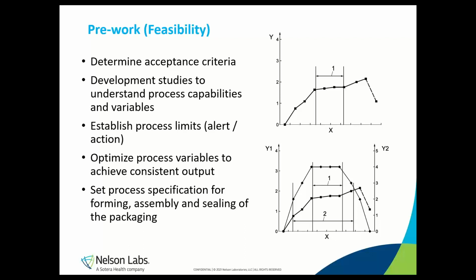I can run some development or feasibility studies to help me understand the process by challenging individual process parameters, and then seeing how changing one variable at a time will affect the final output. In developing my seal strength specification, I might want to seal samples at increasing temperatures and check the peel strength to find the relationship between temperature and strength. These graphs from ISO 16775 show a heat seal curve analysis that was used to develop a processing window as the high and low temperatures that gave a consistent seal strength. The graph on the top is the curve for seal strength. As the temperature is increased, the seal strength increases until it plateaus. This flat area on the curve is the ideal processing window for this material combination.